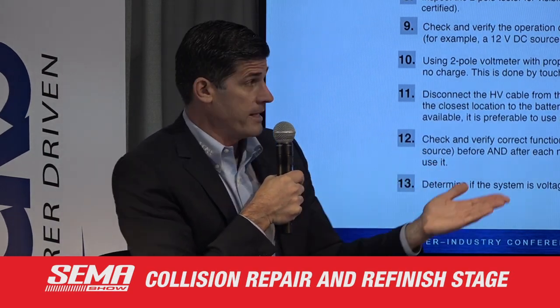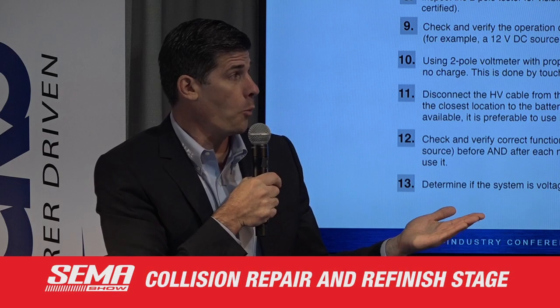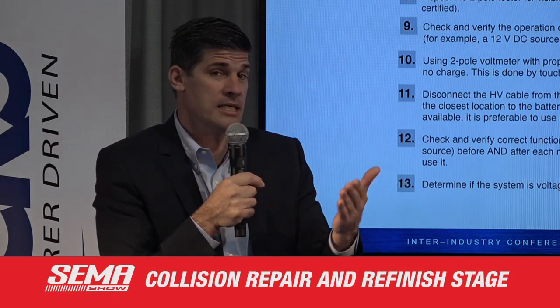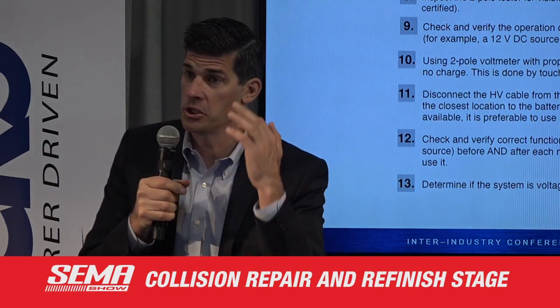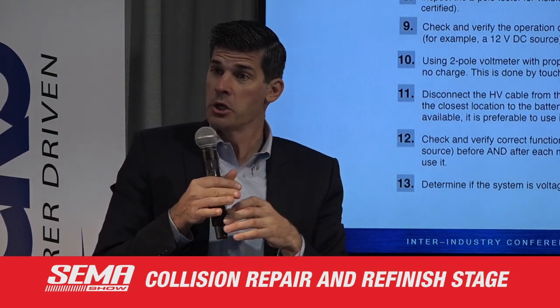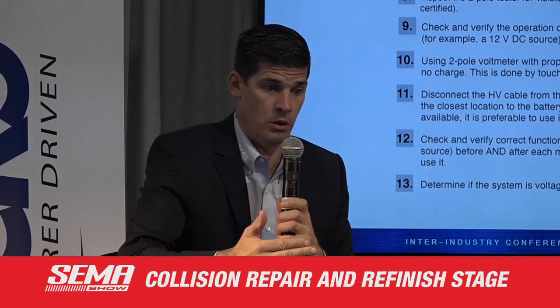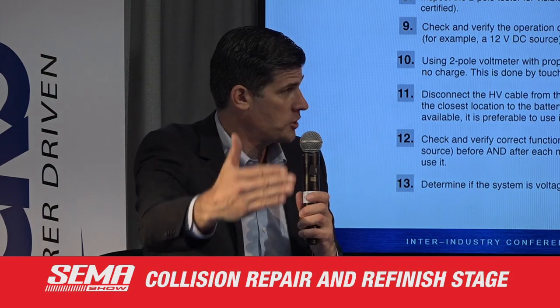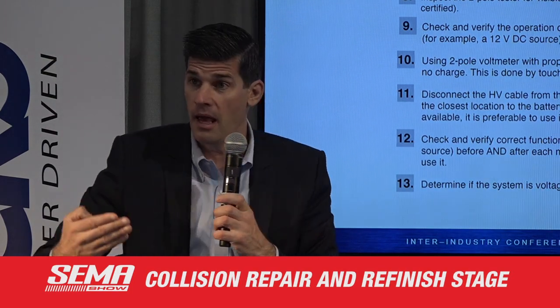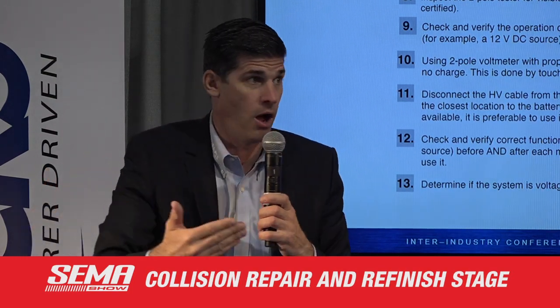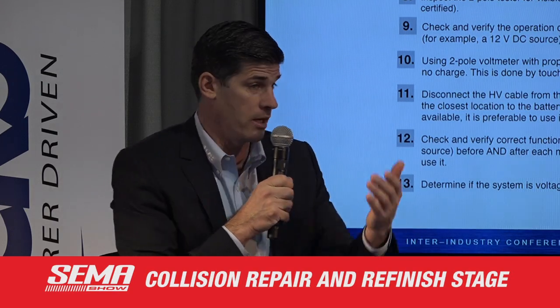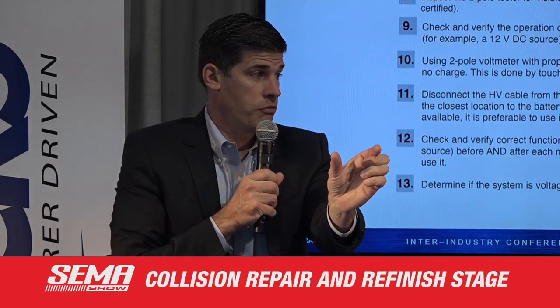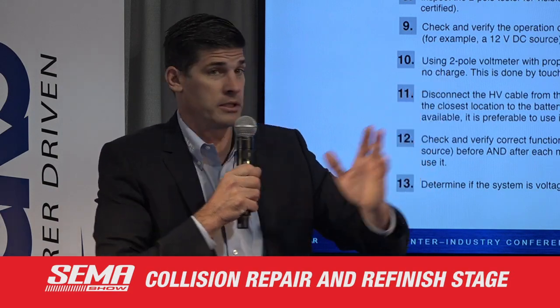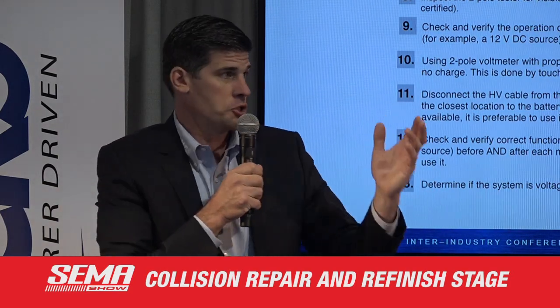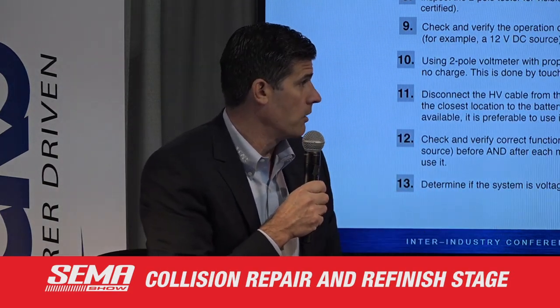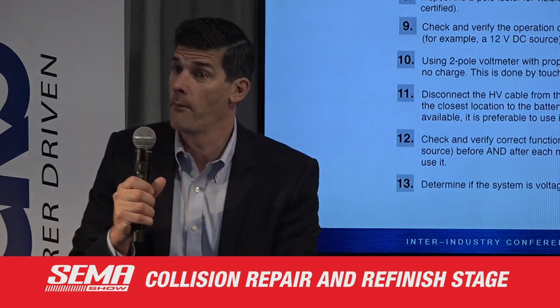On AC mode, it didn't show me any voltage. And this is the risk with high voltage technology. You have to set up your tool on the right setting to measure things, and that could be a big problem. When you make a mistake, you get a reading of 0. You think the world is good, the system is good, and you touch the cable and you are dead. So that's the problem. There is no room for mistakes.